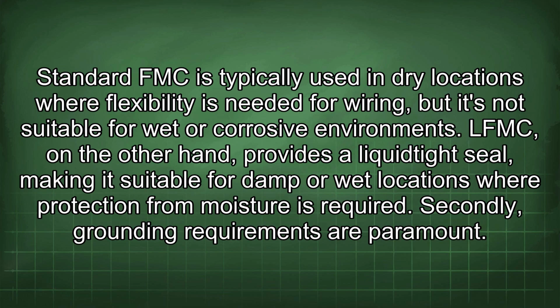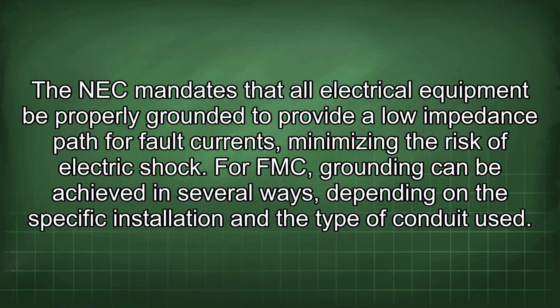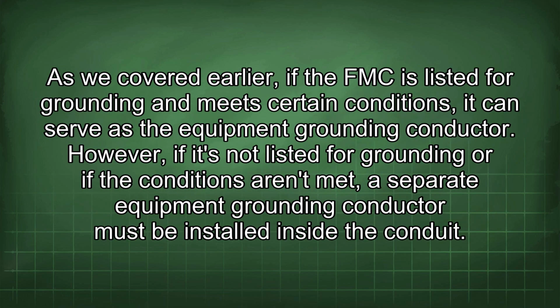Secondly, grounding requirements are paramount. The NEC mandates that all electrical equipment be properly grounded to provide a low impedance path for fault currents, minimizing the risk of electric shock. For FMC, grounding can be achieved in several ways, depending on the specific installation and the type of conduit used. As we covered earlier, if the FMC is listed for grounding and meets certain conditions, it can serve as the equipment grounding conductor. However, if it's not listed for grounding or if the conditions aren't met, a separate equipment grounding conductor must be installed inside the conduit.